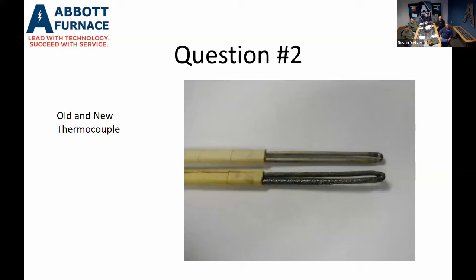So if the question was concerned about calibration, we have a calibration lab here at Abbott that we do bring to some of the guys that are on the phone here. And we do calibrations of the instruments. What we check is the millivolt signal that the thermocouple is putting to the instrument. That is what we check, not so much the calibration of the thermocouple itself.